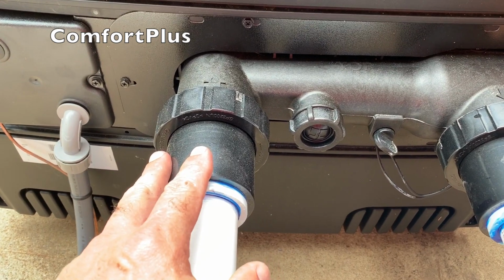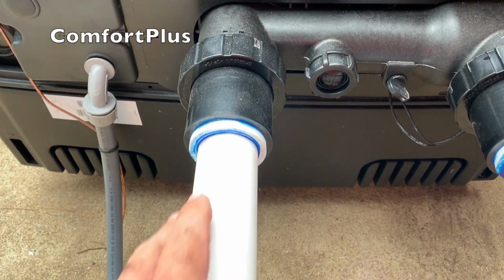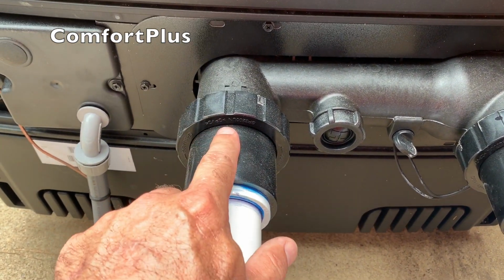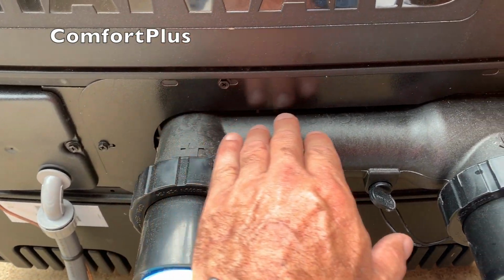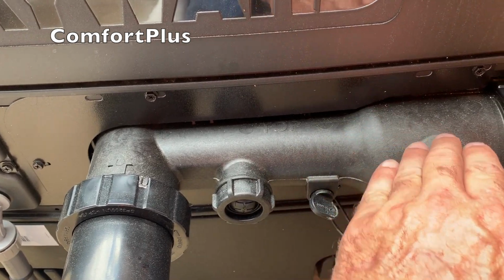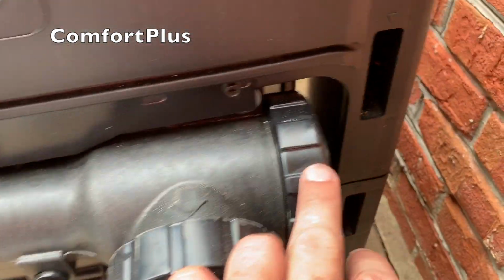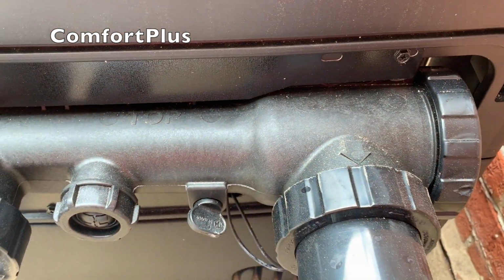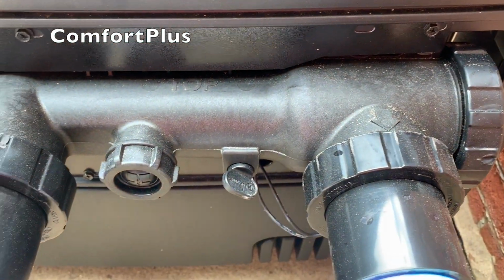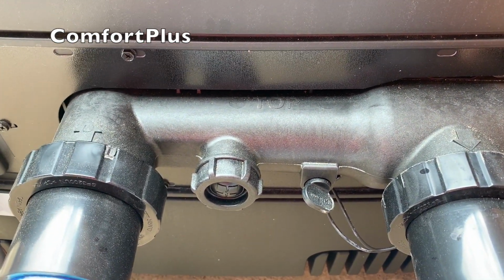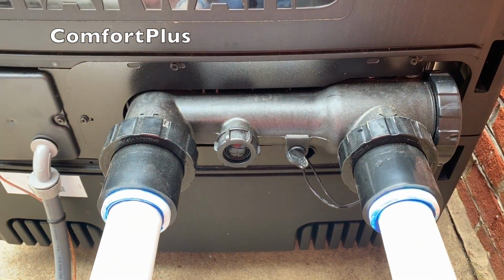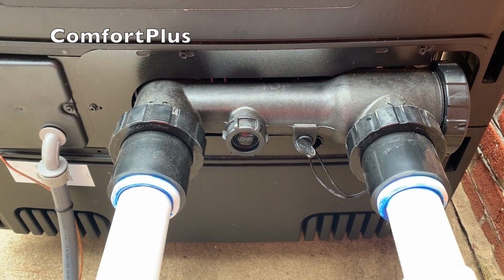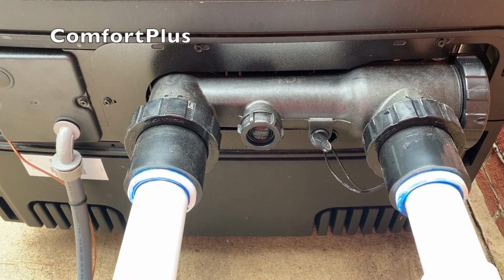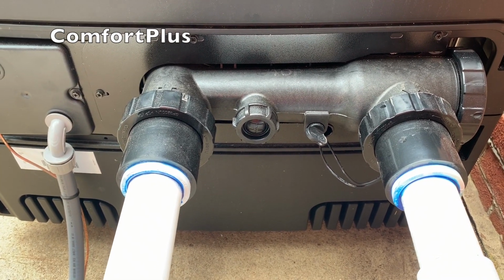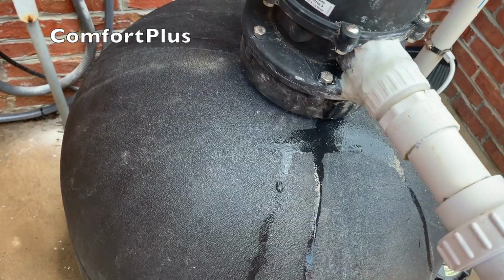Okay, here is the reason I don't need the bypass plumbing that I cut out. The inlet goes in here. Some of the water goes through the heat exchanger, but a large portion of it can bypass the heat exchanger and come right back out. It's got a spring-loaded regulation valve here that allows it to bypass water, so you don't need a manual bypass external to the heater. In fact, it's probably a bad idea because someone can set the valves wrong and not put enough water through the heat exchanger. Leaky filter.